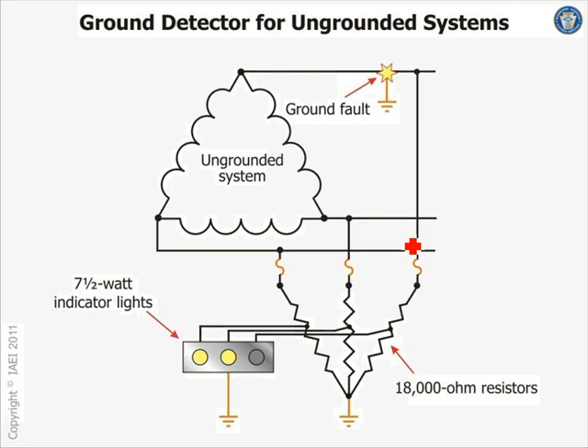But we want you to go eliminate it, because the ground fault will create transients in your system and could escalate to a fire too. You don't want it to sit, number one. Number two, you don't want another ground fault to happen, because then you have a short circuit, phase to phase.